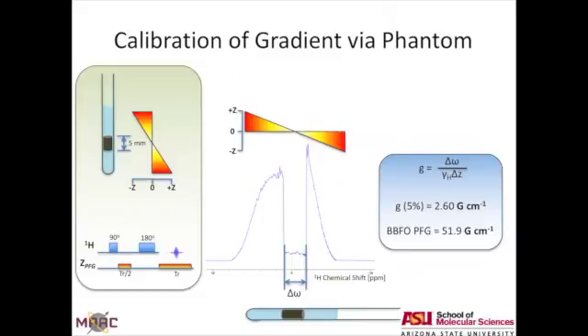So when you're teaching this, it's also a really good idea, a good opportunity to introduce the direct relationship of NMR and MRI to students. Because you're actually going to take advantage of that your NMR can do imaging. And you can use it to calibrate your gradients with a simple phantom in the middle of a known size. And you get this space, this void that's taken away, and you can use it to calculate your strength. But also, what's also equally important in measuring diffusion is not only knowing accurately what the strength of the gradients that your probe provides, but also you need to have a really good control over your temperature in order to do that correctly, in order to get to correct numbers. So typically, when we set up diffusion experiments, we're calibrating on pure D2O at 25 degrees C because we know the diffusion coefficient of that. Use that to completely set up our system.